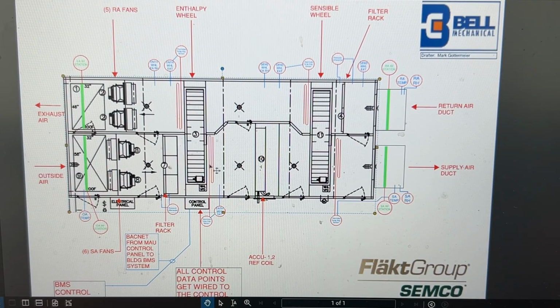And I want to talk about how on this makeup air unit there are two chambers. One is specifically outside air: supply air fans, filter bank, enthalpy wheel. This goes through the AC coil, the sensible wheel, and then it goes off to be supply air for the building. So this will be bringing fresh air to the heat pump system throughout all the floors of the building.